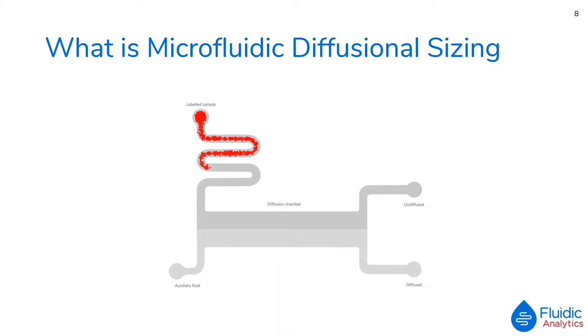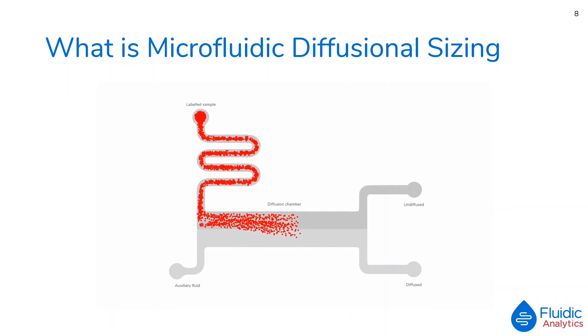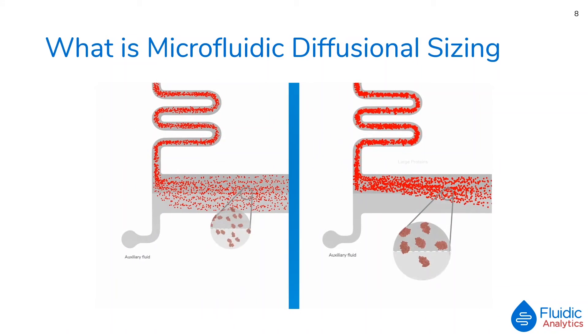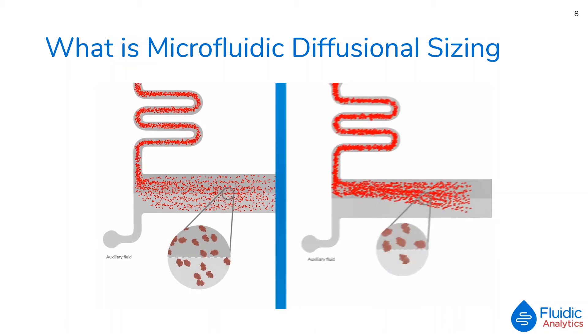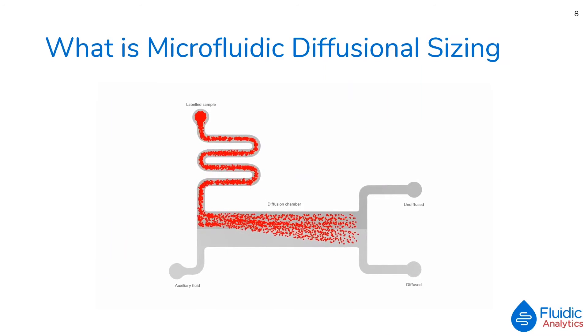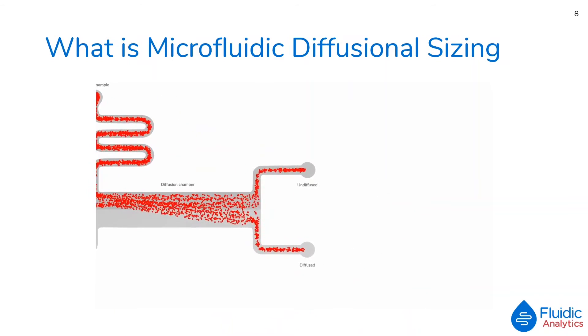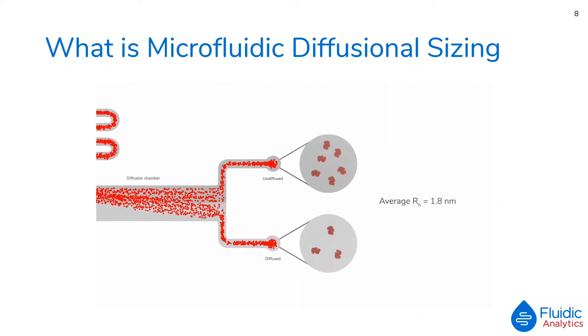The following video explains how microfluidic diffusional sizing works. In the Fluidity One-W, a stream of fluorescently labelled protein is introduced into the diffusion chamber alongside an auxiliary stream. These streams flow in parallel with no convective mixing, so the only way protein can migrate from one stream to the other is by diffusion. Small peptides and proteins diffuse rapidly; large proteins and aggregates diffuse slowly. At the end of the diffusion chamber the streams are split, and the quantity of protein in each stream is determined by the fluorescence from the label.